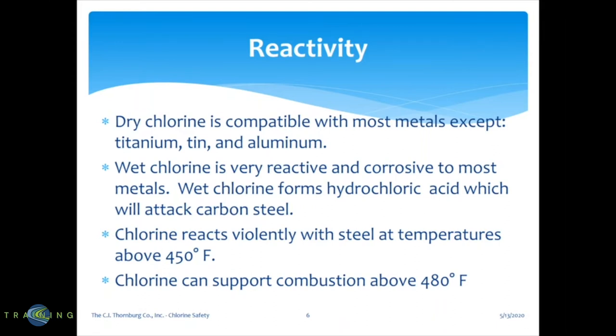Chlorine reacts violently with steel at temperatures above 450 degrees Fahrenheit. So if you have a fire in your chlorine storage room, the reaction is very violent. It won't explode, but it will definitely make the fire hotter. Chlorine can also support combustion above 480 degrees Fahrenheit.